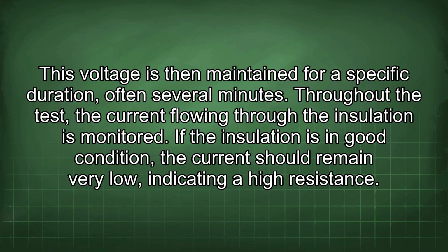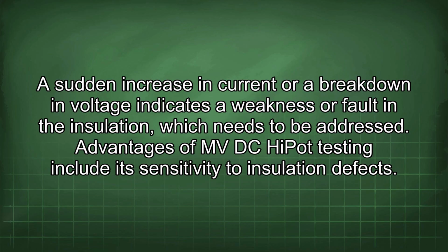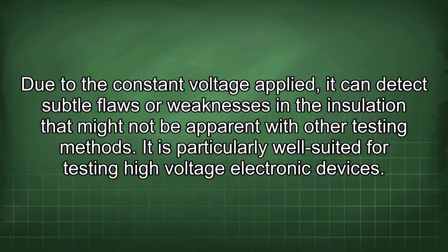Throughout the test, the current flowing through the insulation is monitored. If the insulation is in good condition, the current should remain very low, indicating high resistance. A sudden increase in current or a breakdown in voltage indicates a weakness or fault in the insulation which needs to be addressed. Advantages of MVDC HiPot testing include its sensitivity to insulation defects. Due to the constant voltage applied, it can detect subtle flaws or weaknesses in the insulation that might not be apparent with other testing methods.